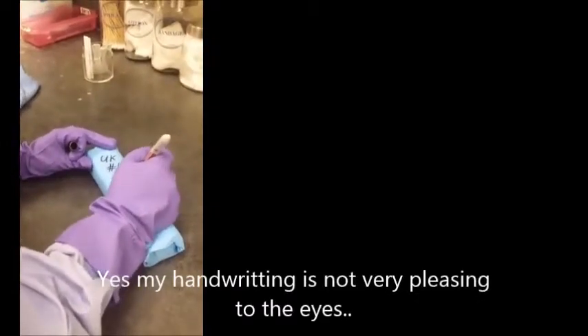Make sure to use the autoclave tape and not the masking tape. The autoclave tape is the one with the stripes and will change color once a certain temperature in the autoclave has been reached. Once the cassette is wrapped, take a marker from the dirty container. Put your initials, locker number, and today's date. The cassette is now ready to be autoclaved.